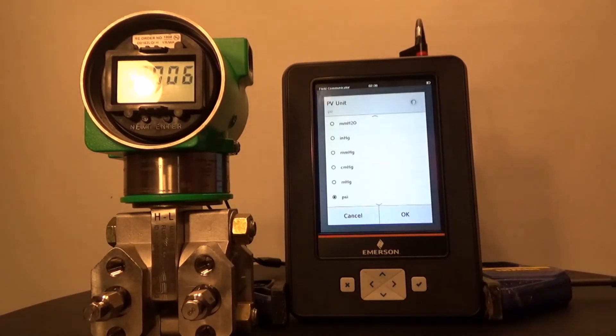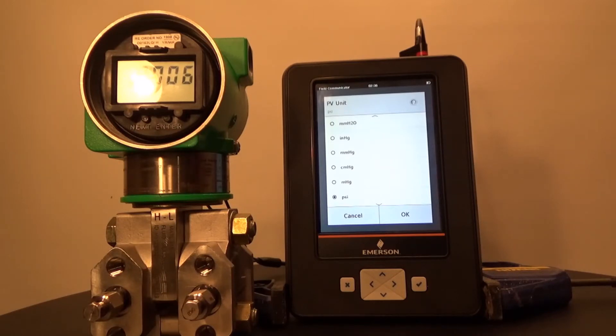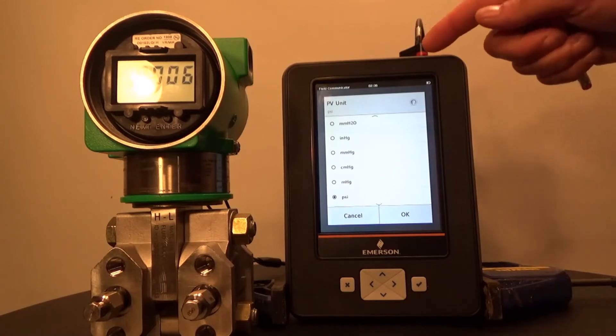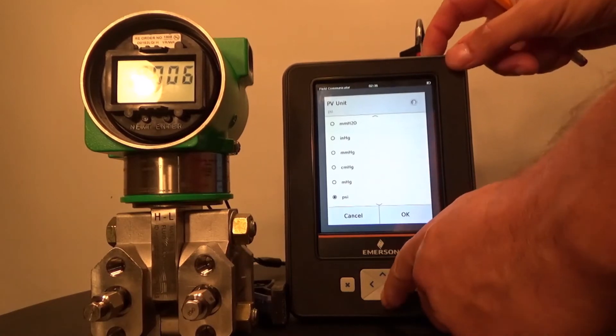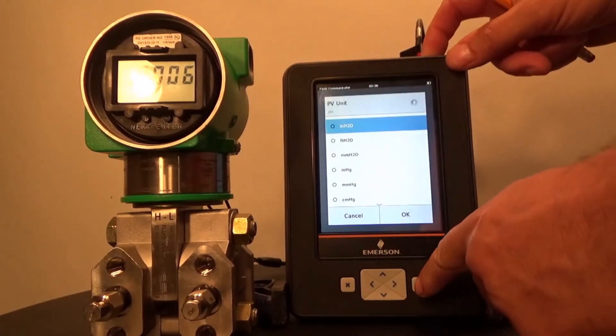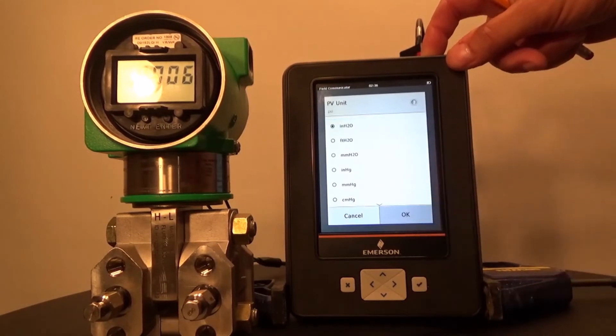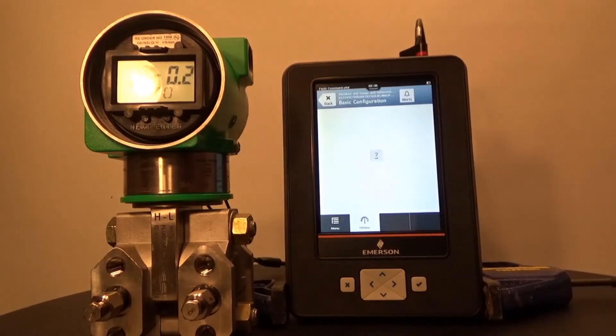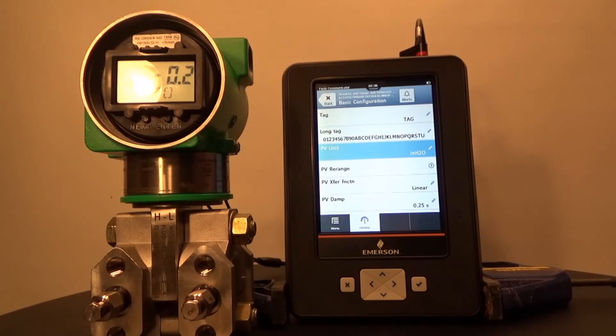Then select the required PV unit for the application — this is the differential pressure PV unit. In our example it will be inches of water, so we scroll until inches of water is highlighted, press the check mark, then press OK. We will be routed back to the Basic Configuration menu.